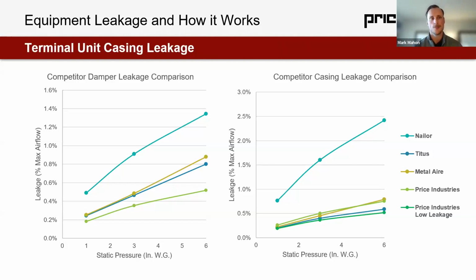And when we look at the damper leakage, really Metal Aire, Titus, Price, negligibly different as far as the way they actually perform. We're looking at close to testing tolerance when we look at some of these percentages. I'll still raise my hand and be happy to say Price is at the bottom of the curve. We like to see that as a manufacturer, but really negligible differences there. Nailor a little bit higher, starting to be maybe something measurable or something to consider when choosing equipment.